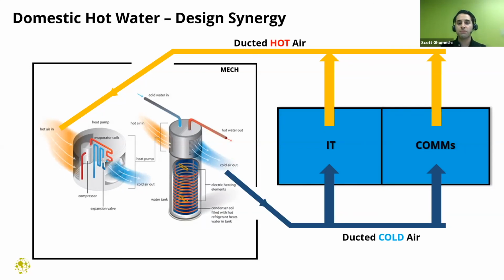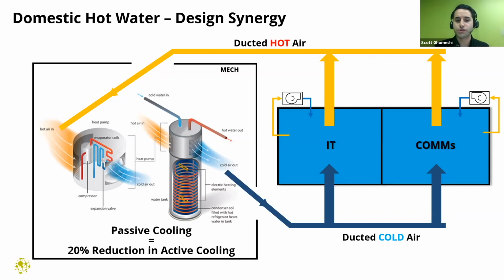Doing some back-of-the-envelope calculations, based on the amount of domestic hot water consumption forecast for this building, the amount of cooling that's able to be offset—since we'll still need fan coils, as we won't be utilizing domestic hot water all the time, so fan coils will always help manage the load—this approach would probably help reduce the amount of active cooling these spaces need by about 20%. Over the course of a year that's quite substantial, considering this is a 24/7 load constantly imposed on the building.